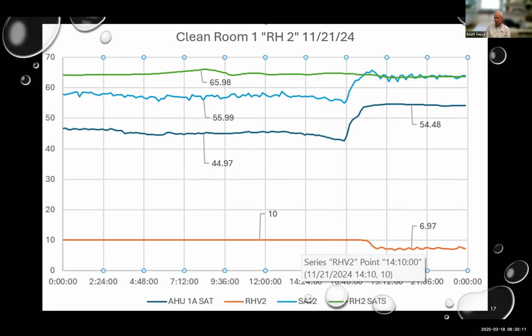Trending should be done in cold weather for perimeter systems, but it is not absolutely necessary to test at the design temperatures, as the response at design conditions could be extrapolated. Our winter design temperature, which is the outside air temperature of 10 degrees Fahrenheit, we find that testing the perimeter heating equipment at 20 or 25 seems adequate.